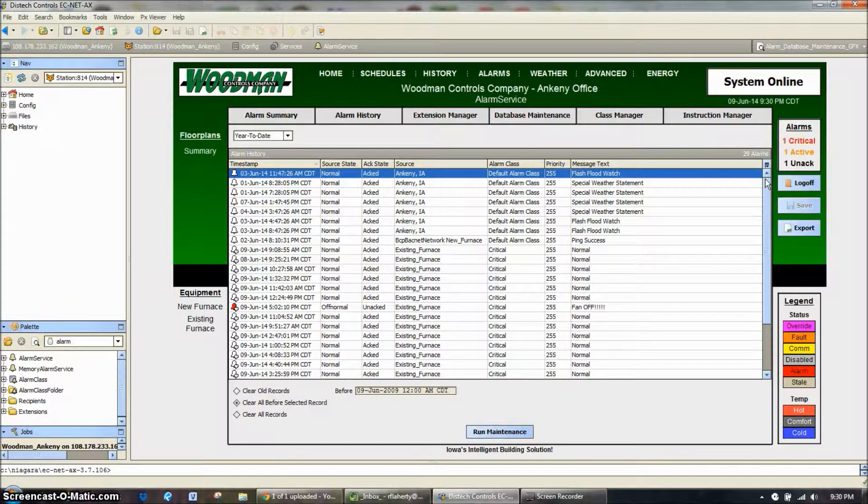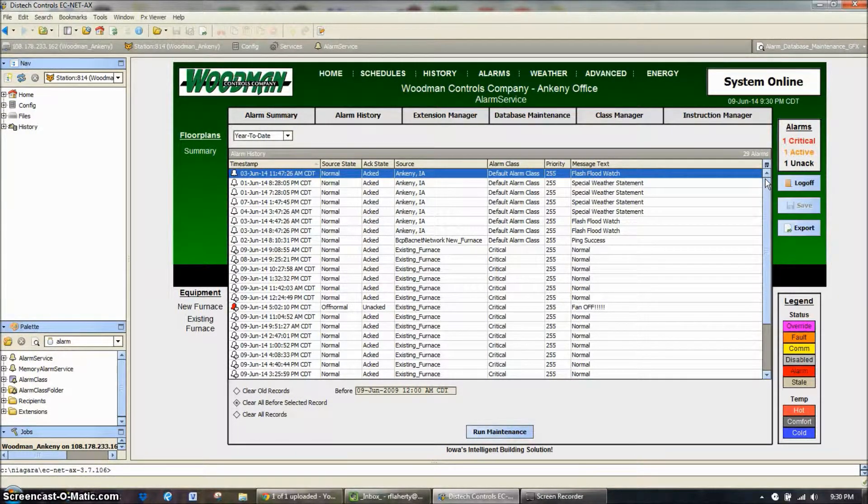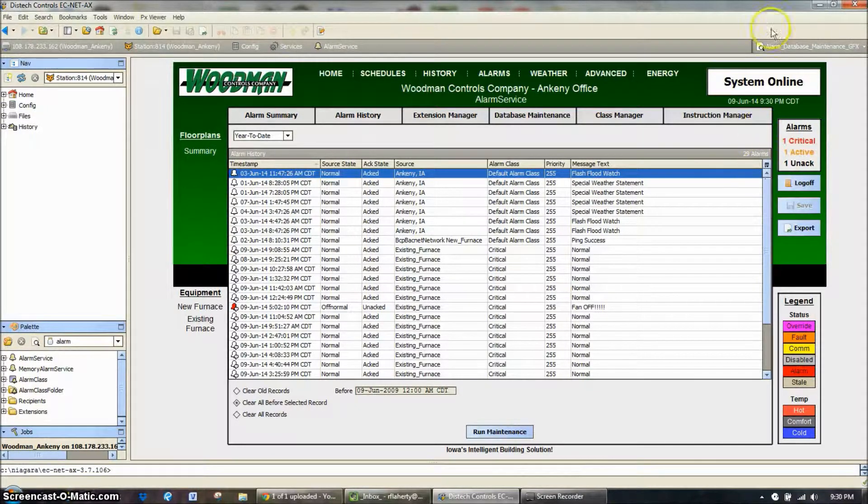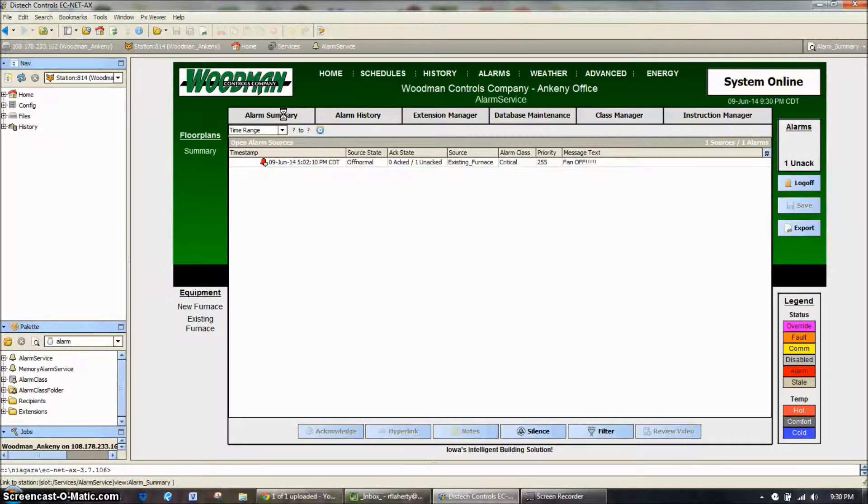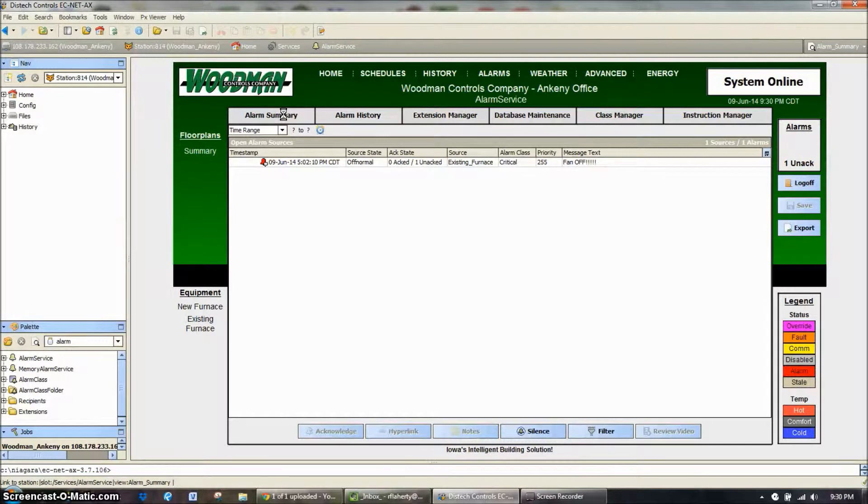But you can see now, you can hunt down your issues. You should see repeated alarms that one that has gone in and out of alarm multiple times. Usually those are the ones that you need to go find, track down and see if there's a mechanical issue or a service issue that needs to be taken care of.